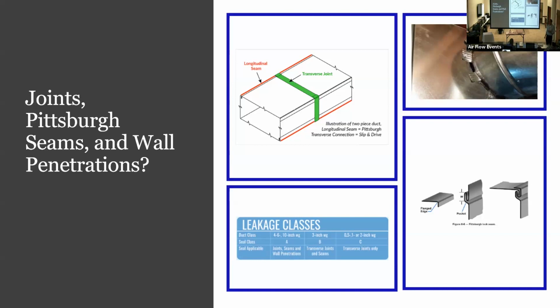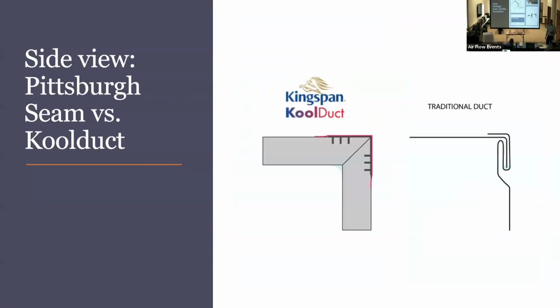All right, so seal class A, that longitudinal seam where we fold up our duct, there could be two seams, there could be one seam, there could be more if it's really big, and then transverse joint and then the walls. Okay, moving on. Notice, some of the duct machines, I don't know if you can see this, there's a little blue thing here. They'll put a little bit of sealer in the machine right when they fold it up. So imagine a contractor that's got a coil line with a sealer built into it, probably always seals up that joint, which is good.